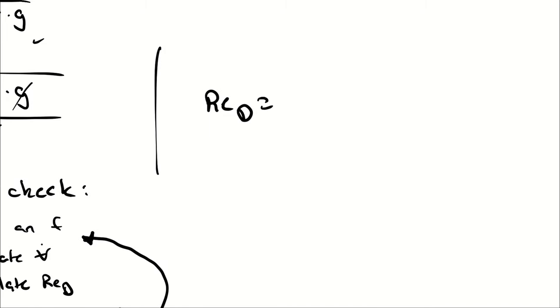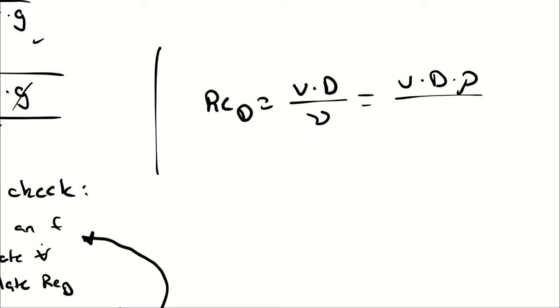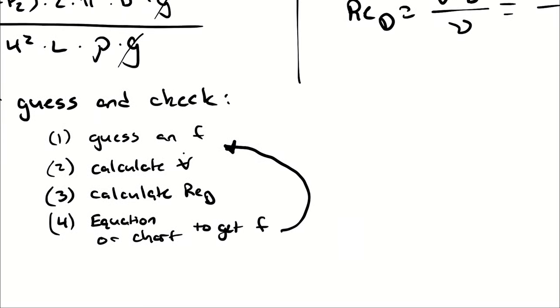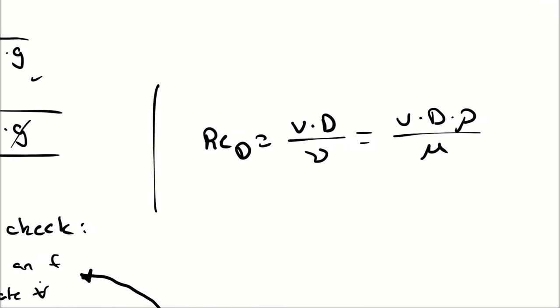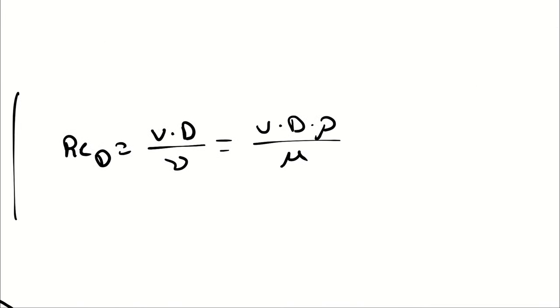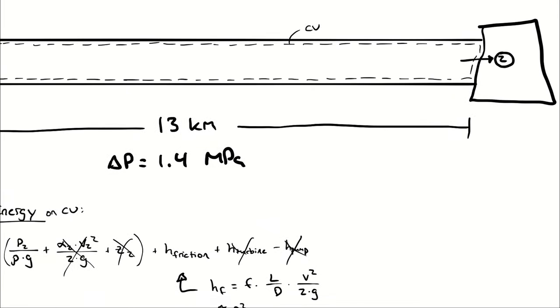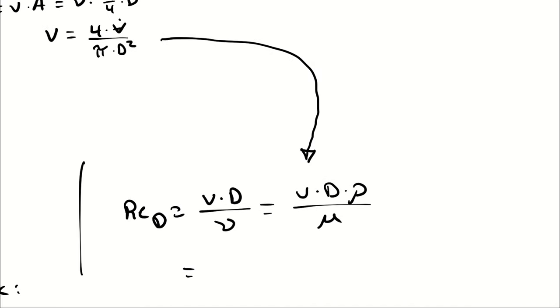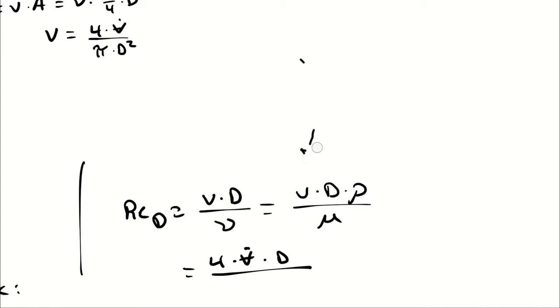The Reynolds number equation is Re = VD/ν or VDρ/μ. Writing in terms of Q rather than velocity (to reduce iteration steps), the Reynolds number becomes 4Qρ/(μπD), using dynamic viscosity form since the table may not provide kinematic viscosity.